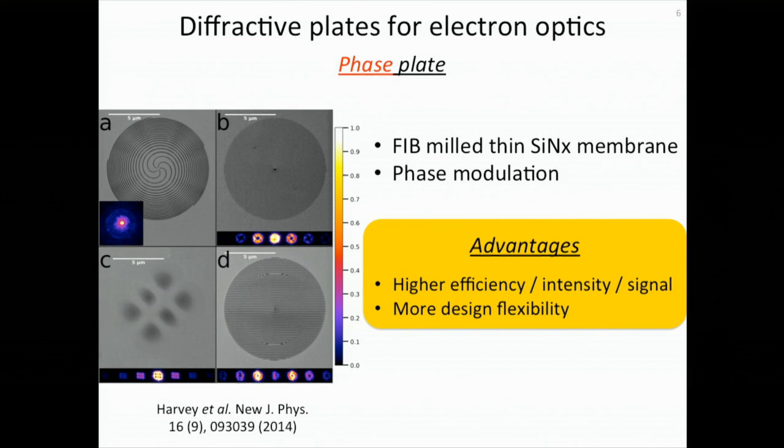Recently, people are more interested in a phase plate, which, according to its name, imposes a phase modulation instead of an amplitude modulation to the incoming electron beam. This slide shows some examples of phase plates made by silicon nitride membrane milled by focused ion beam. There are some advantages of phase plates compared to amplitude plates. First, because all the electrons can transmit through the phase plates, it will give a higher efficiency, with higher intensity and more signal-to-noise ratio in a diffracted beam. Also, the phase plate has more design flexibility, because for an amplitude plate, it either blocks the electron beam or transmits the electron beam. But for a phase plate, we can impose an arbitrary phase shift from 0 to 2π to the incoming electron beam.